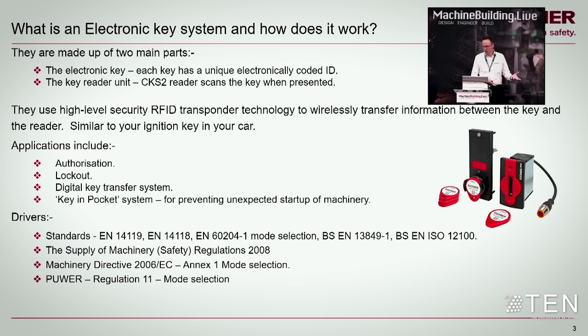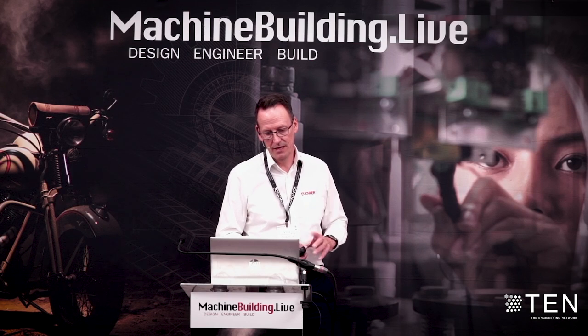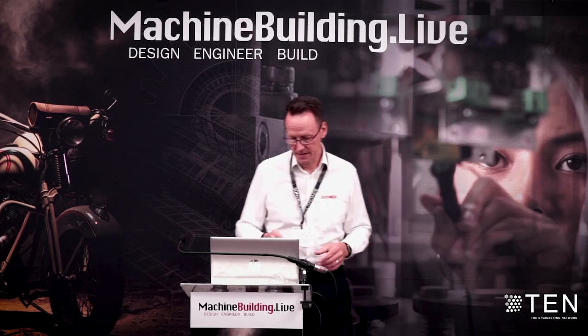Some of the drivers around this are the key legislation in the UK, which is the Supply of Machinery Safety Regulations. That's a legal requirement in the UK that we need to satisfy the essential health and safety requirements of. To help us do that, we have standards, and some of those standards are a key driver or an influencer with the use of this technology now. So 14119 being the interlocking, 14118 is inadvertent startup of machines. It's a real key benefit for addressing that issue, and it links nicely into 13849 and some of the updates around that standard. It's also part of the Provision and Use of Work Equipment Regulations for mode selection. So when we're using our work equipment, it offers a benefit there as well.